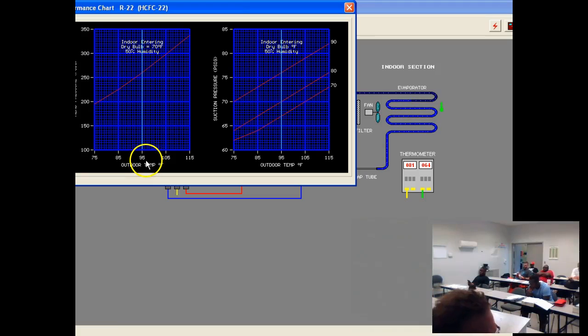So I'm a good bit above it, right? So I would expect to be above the red line, right? Let's see. What's my outdoor temperature? Ambient outside is 95, so I find where 95 and 70 cross. And if it was just 70, I would read it right across from about 260, but I'm higher than 70, right? So I'm going to anticipate a little bit above this red line, read over, about 275, right? Same way, now with the indoor, do you see I have 3 lines? I don't know if y'all can see the 3 lines over here. So I've got a 70, an 80, and a 90, okay? And so they give us a little more chance to be accurate there, okay? So there's our performance chart.